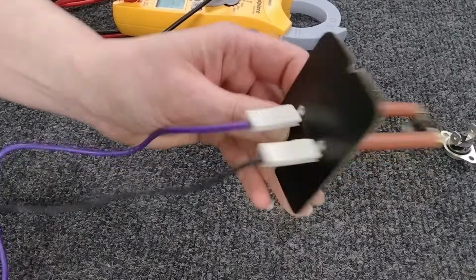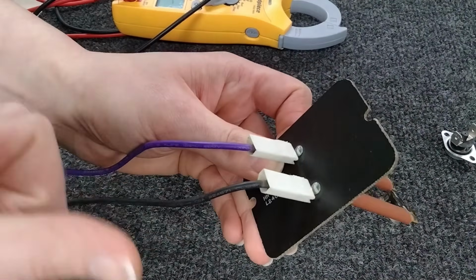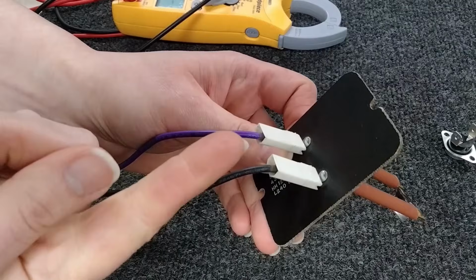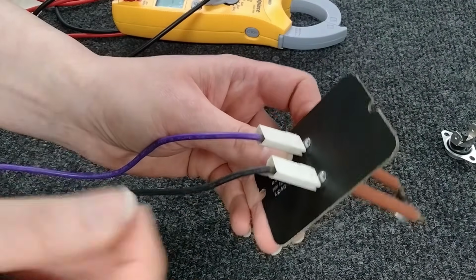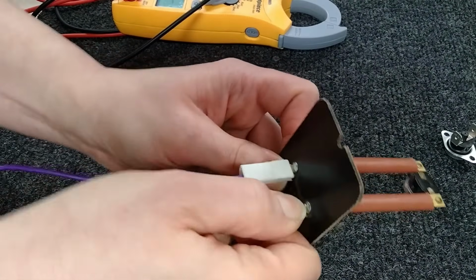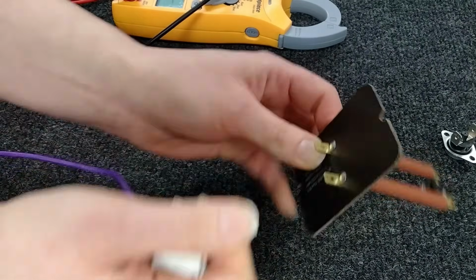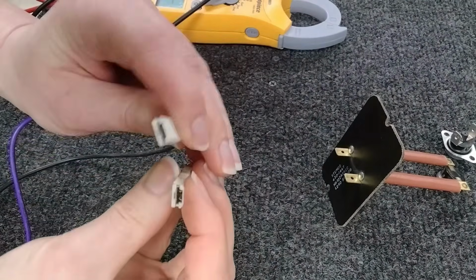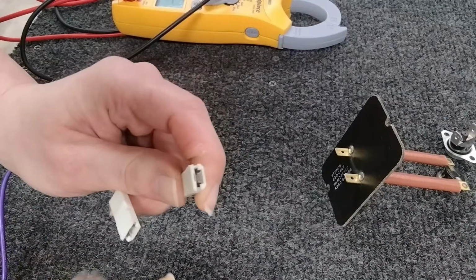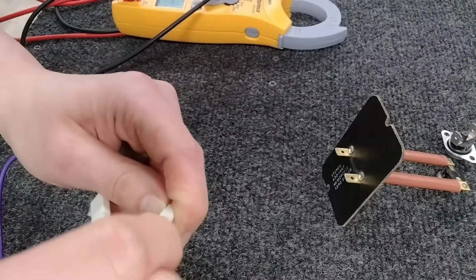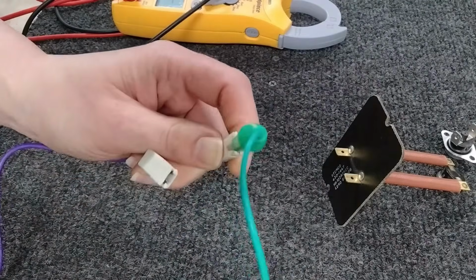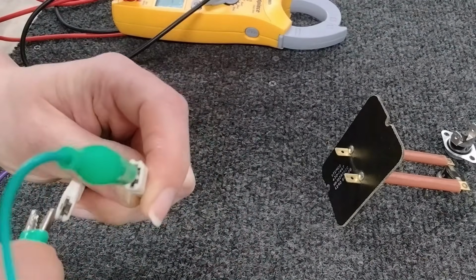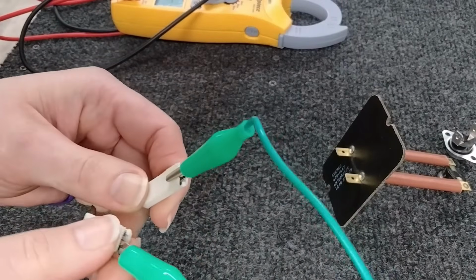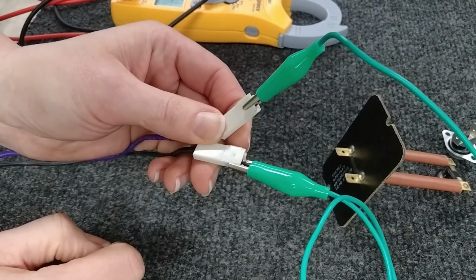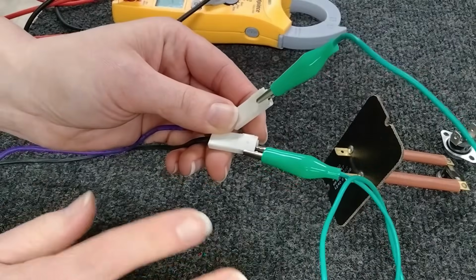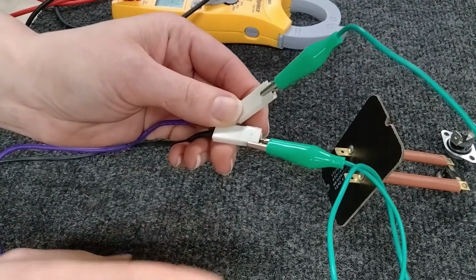So just to review, the two wires coming off of your high limit, whether it be your high limit, your rollout limits, your disc limits, you're going to remove those. Obviously, make sure the power is off before you do this, please. You're going to connect these two, bypassing the need for your limit switch to already have it closed in the unit. There we go. Now we've closed the line. Boop, see if it works just like normal. Now this doesn't always work for diagnosis, and we'll get to why.